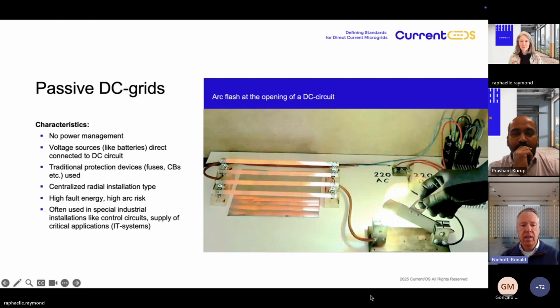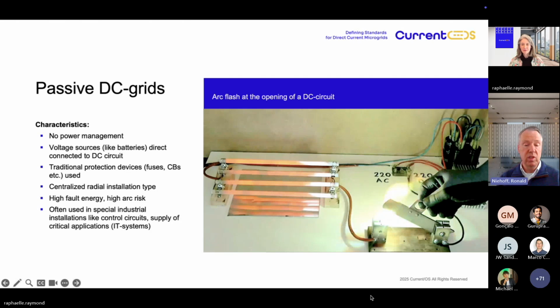Passive DC grids are characterized by no power management. They are the traditional installations since decades. There are mainly voltage sources like batteries directly connected to DC circuits. Mostly traditional protection devices like fuses and circuit breakers are used. The architecture of the installations is mostly centralized radial. There is a high fault energy and a high arc risk in such installations, and they were often used in the past, but also still for control systems, supply of critical applications like in IT systems, etc.